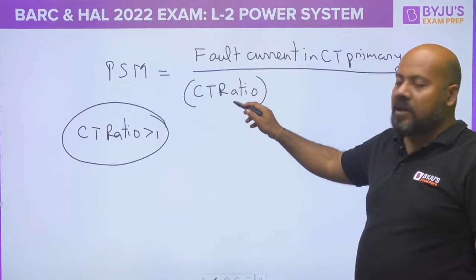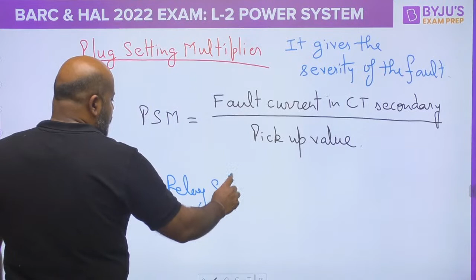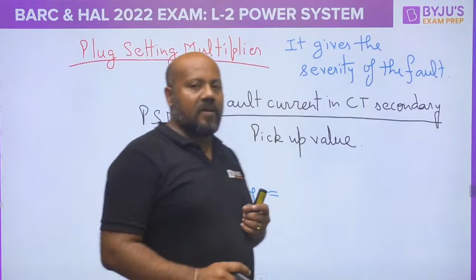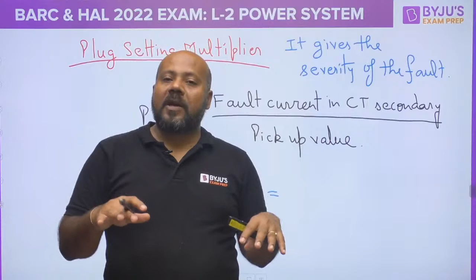We are taking the sample of the current from there. So the CT secondary value of the fault current is going to be a lesser value. What you have done, you have written a higher value. It should be a lower value. How can you transform it into a lower value? Just use the CT ratio like this. Just divide it by the CT ratio, but this CT ratio must be more than 1. You define the CT ratio of the current transformer so that it is more than 1. So if you divide this higher value by something which is more than 1, definitely you will get a lesser value, and that is nothing but the fault current in the CT secondary.